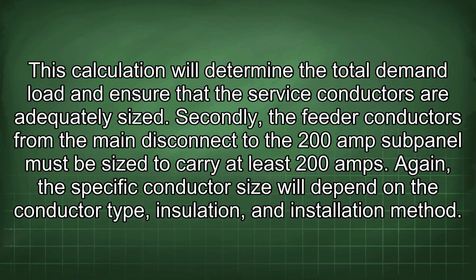This calculation will determine the total demand load and ensure that the service conductors are adequately sized. Secondly, the feeder conductors from the main disconnect to the 200 amp subpanel must be sized to carry at least 200 amps. Again, the specific conductor size will depend on the conductor type, insulation, and installation method.